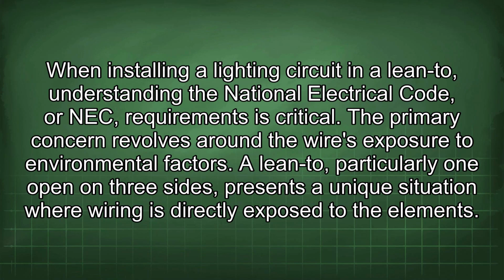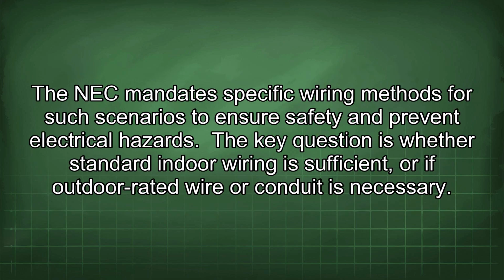When installing a lighting circuit in a lean-to, understanding the National Electrical Code, or NEC, requirements is critical. The primary concern revolves around the wire's exposure to environmental factors. A lean-to, particularly one open on three sides, presents a unique situation where wiring is directly exposed to the elements. The NEC mandates specific wiring methods for such scenarios to ensure safety and prevent electrical hazards. The key question is whether standard indoor wiring is sufficient, or if outdoor rated wire or conduit is necessary.